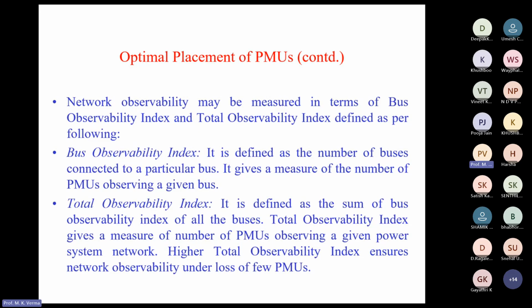So this PMU placement was considered based on total observability index. The bus observability index was defined as the number of buses connected to a particular bus. So if you put a PMU at any particular bus, and this bus is connected to other buses, we can calculate the voltage of the other buses. So there is no need of putting PMUs at those buses. And the total observability index is the summation of bus observability indices. And this total observability index should be high enough so that even if a few PMUs are lost, we should still be able to observe the system, the health of the system.